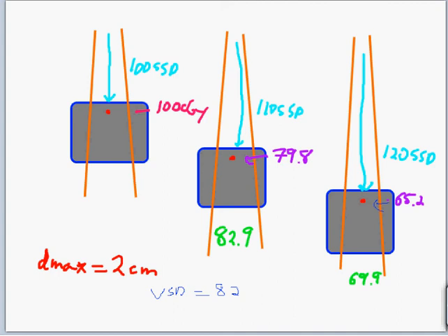However, I should point out that this is only good for a very short range. In other words, if you went beyond 120, it's probably going to break down. The electrons are going to scatter quite a bit. So you'd really only use it in the range of, say, 100 to 120. You wouldn't use it if you're trying to treat somebody across the room. You shouldn't do that with electrons anyway, but it wouldn't hold up. It only works for a very short range because the electrons are really not falling off according to inverse square.